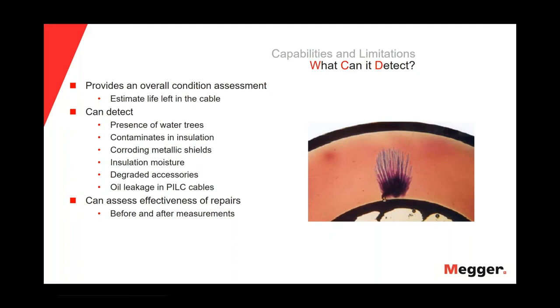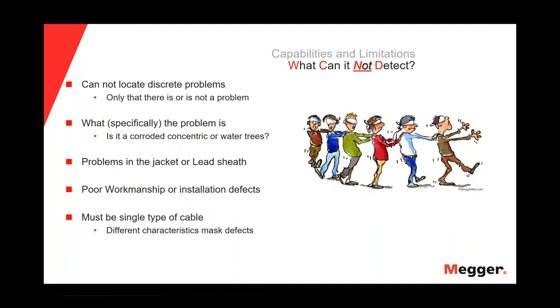So what can it not detect? What can we not see with the tan delta? Well, we cannot locate discrete problems, only whether there is or is not a problem. For instance, if we have very high, very bad values in a tan delta test, we could not say if the problem comes from a corroded concentric or from water trees. That would be quite difficult to know by only doing the tan delta test.